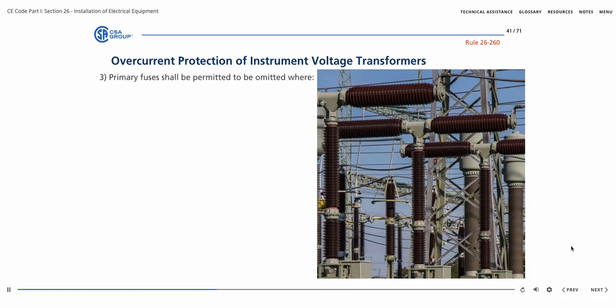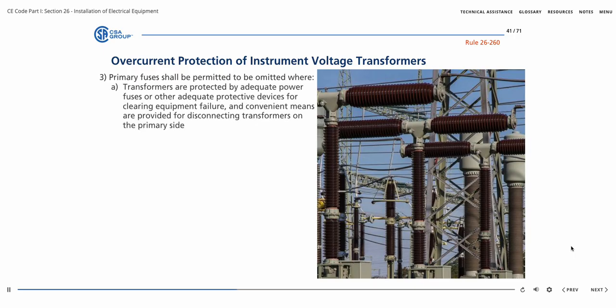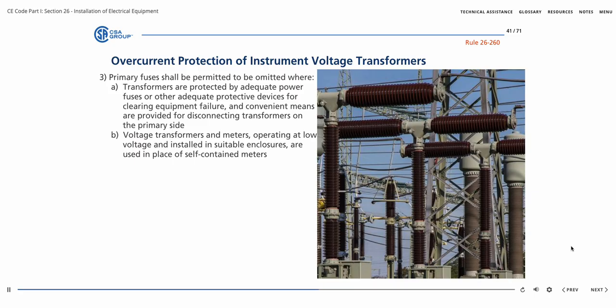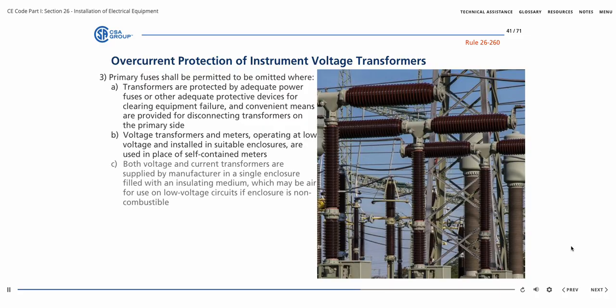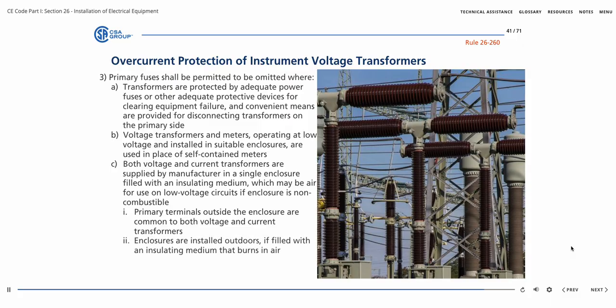3. Primary fuses shall be permitted to be omitted. A. Where the transformers are protected by adequate power fuses or other adequate protective devices for clearing equipment failure, and convenient means are provided for disconnecting the transformers on the primary side. B. Where voltage transformers and meters, operating at low voltage and installed in suitable enclosures, are used in place of self-contained meters, or C. Where both voltage and current transformers are supplied by the manufacturer in a single enclosure filled with an insulating medium, which may be air for use on low voltage circuits if the enclosure is non-combustible, and where 1. The primary terminals outside the enclosure are common to both voltage and current transformers, and 2. The enclosures are installed outdoors if filled with an insulating medium that will burn in air.